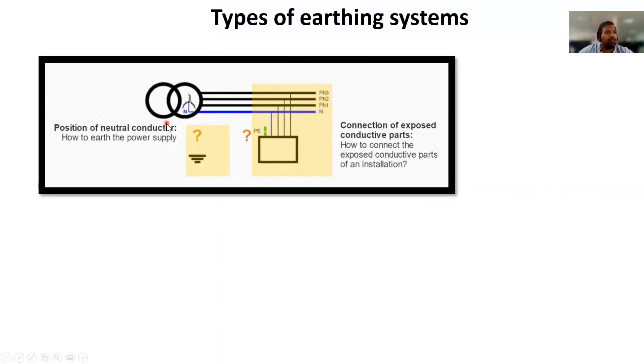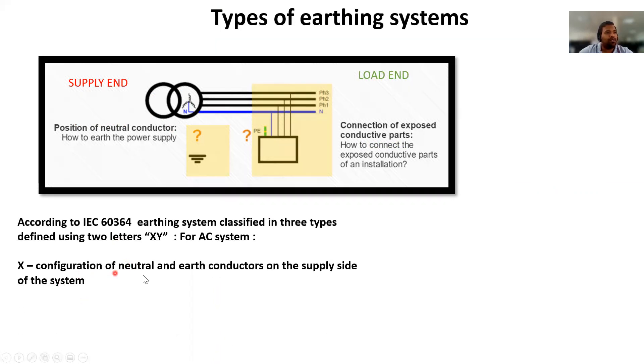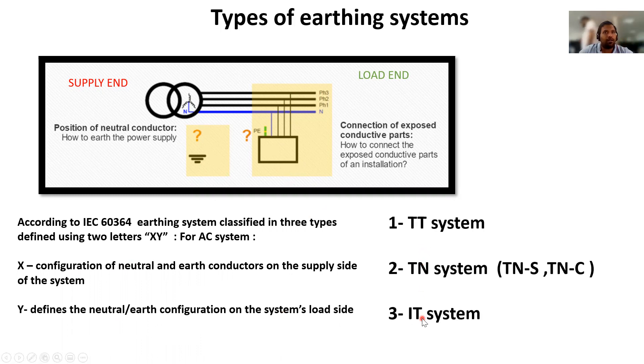Types of earthing systems: Looking at a typical diagram with a supply transformer on one side and load-side equipment on the other, according to IEC 60364, earthing systems are classified based on how the supply-side neutral and earth conductors are configured, as well as how the load-side neutral is arranged. There are three types: TT system, TN system, and IT system.